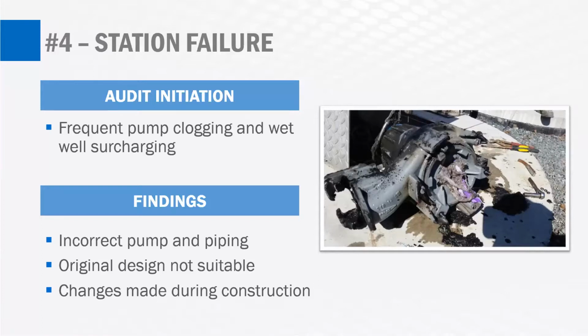An audit was performed and found issues basically every step of the way. One of the biggest alarming issues that was found is the incorrect pump and piping were installed in this pump station. I actually was on site for this audit. We opened up the wet well, and when we saw the piping in the wet well, which was 1.5 inch PVC piping, and we were expecting 3-inch ductile iron piping, it was very eye-opening, and alarm bells started ringing in everybody's heads.